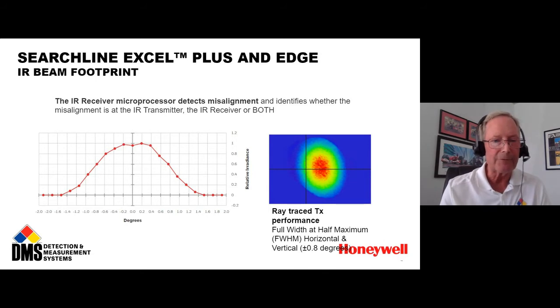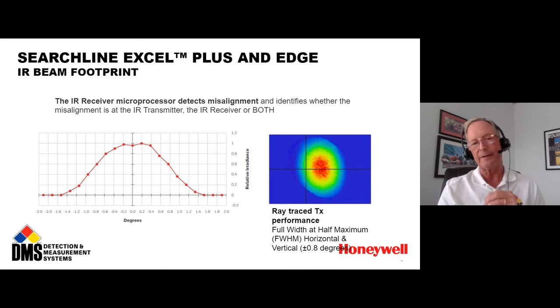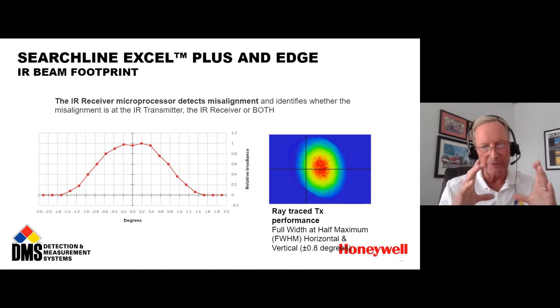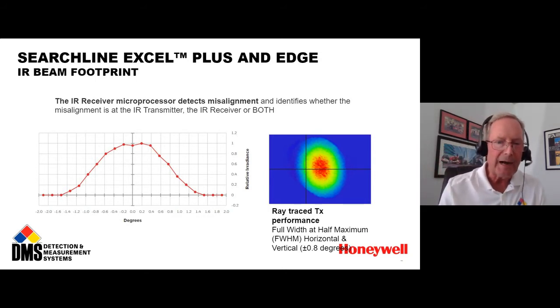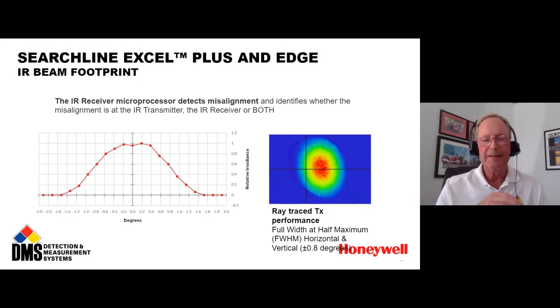If you look at the chart to the left, what's really interesting is, first of all, that surface of that intense portion of the beam is very flat. So that's a nice, flat, broad, and I say broad, it's basically 0.4 degrees on either side of the sweet spot of that beam intensity, which is a large area of beam to align the detector on. So it actually means that the detector can be aligned very easily to this large sweet spot of high intensity IR. You'll see the IR light drops off, and at about 8.8 degrees on either side, you're at about 50% of the light intensity that you get at the center, which is still more than ample light for the detector to work if you have misalignment.